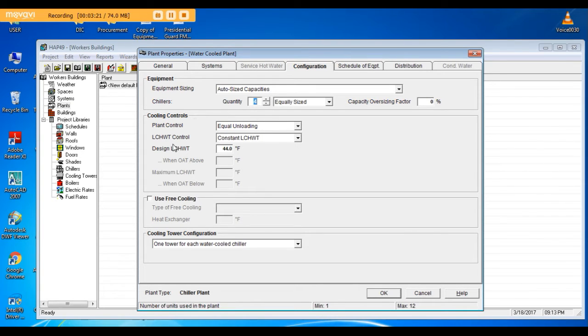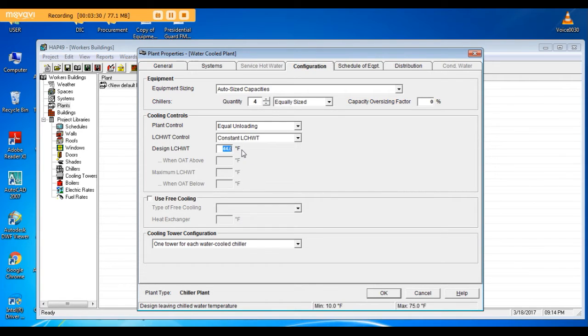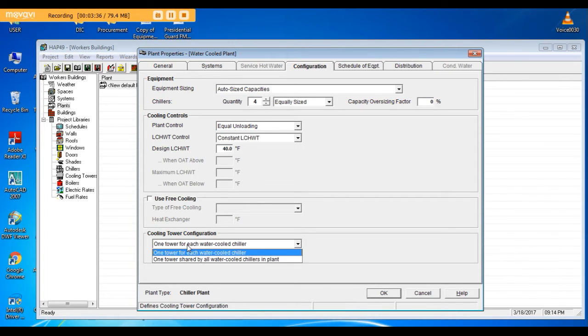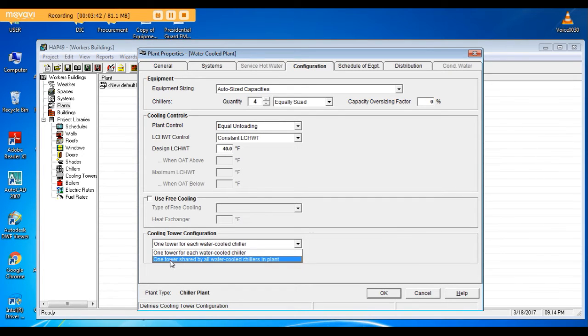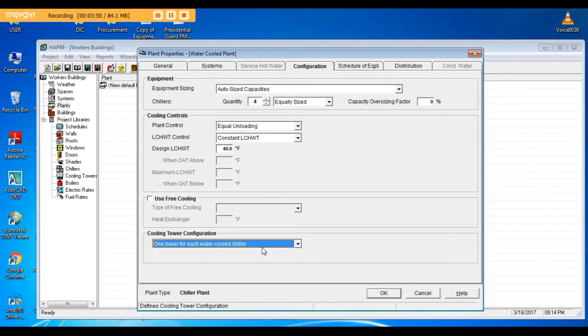Leaving chilled water control: constant leaving chilled water. The design leaving chilled water temperature I needed 40 degrees Fahrenheit. Here you can choose one cooling tower for each water cooler or one tower shared by two or four chillers. I will choose one tower for each chiller, so we have four cooling towers.